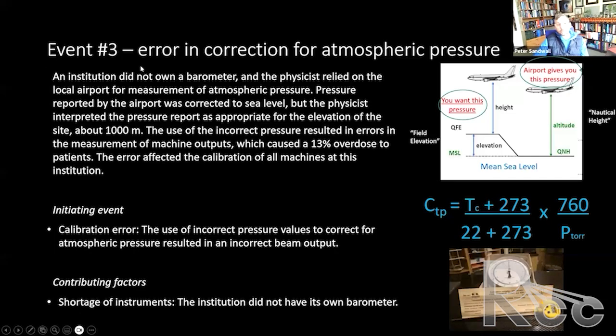So here's another one. Event 3, an error in correction for atmospheric pressure. This is a classic one. We like to use this as a board question, but an institution did not own a barometer, and the physicist relied on the local airport for measurement of atmospheric pressure. Pressure reported by the airport is corrected to sea level. It's not at the local altitude. So the physicist interpreted the pressure report as appropriate for the elevation of the site, about 1,000 meters. And so the use of the incorrect pressure resulted in errors, which caused a 13% overdose to patients.